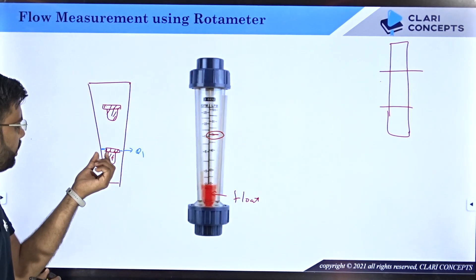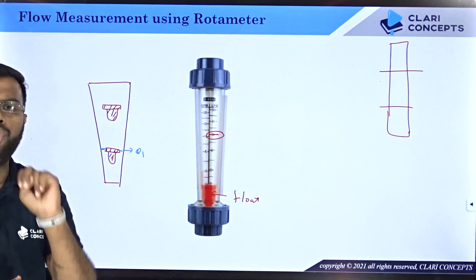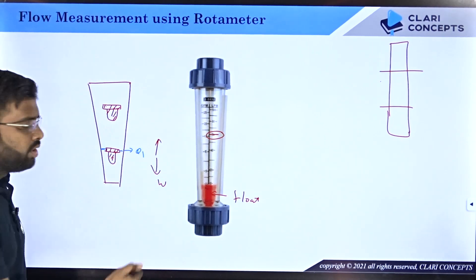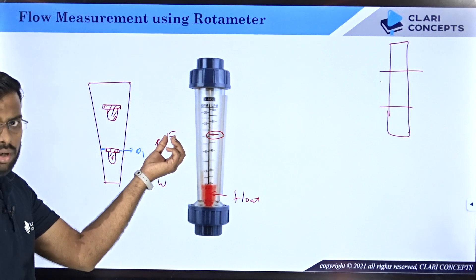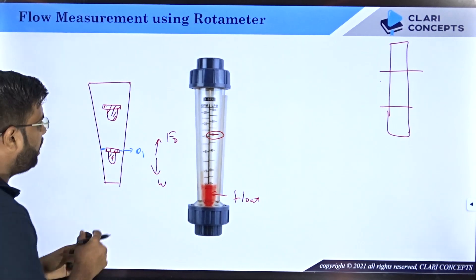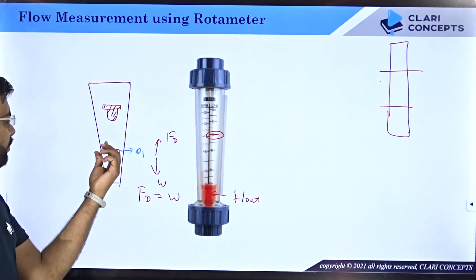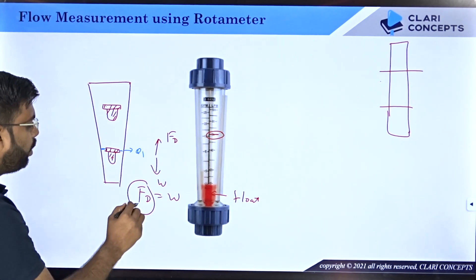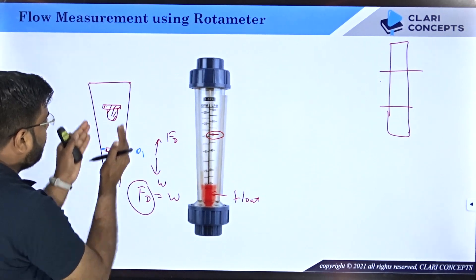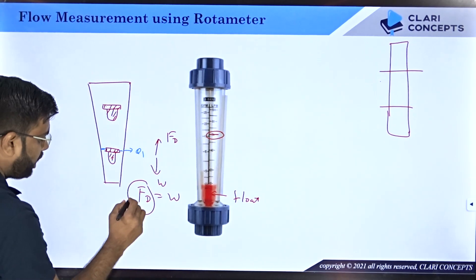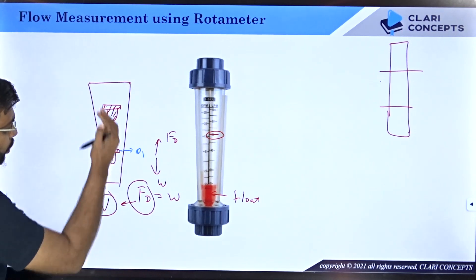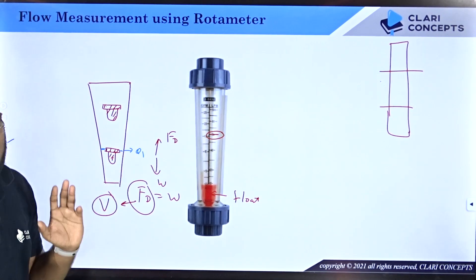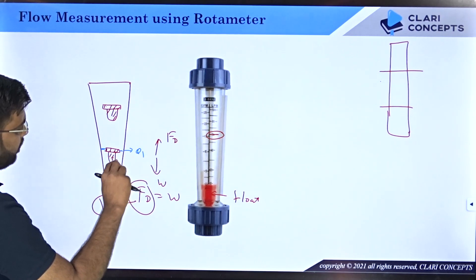When the float is floating at a particular height, two forces act on it: its weight W acting downward, and the drag force Fd from the water acting upward. When the float is in equilibrium, drag force equals weight. Since the weight of the float is always fixed, the drag force is always fixed when floating. The drag force depends on the velocity of water flowing over and around the float, so there is a specific velocity v at which the float experiences that fixed drag force and floats in equilibrium.